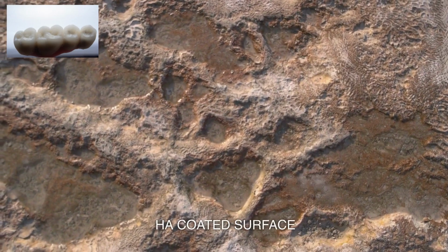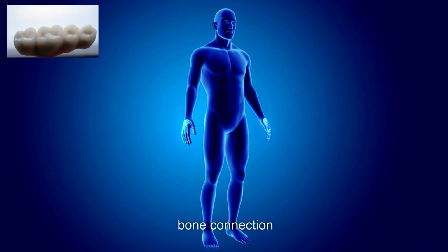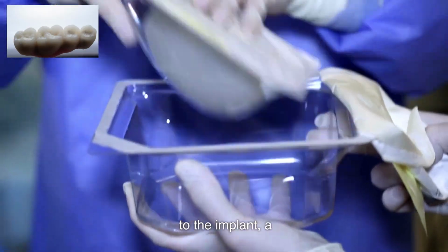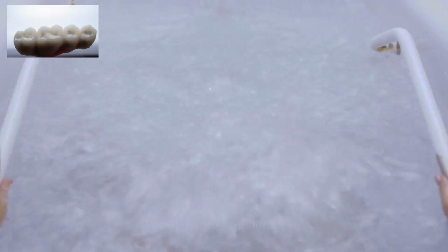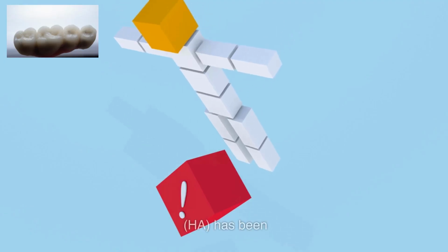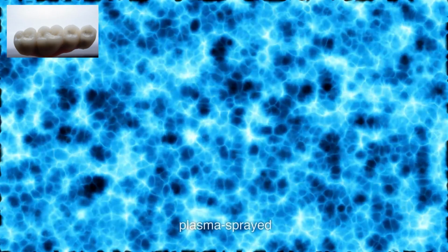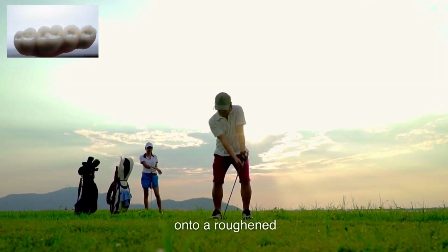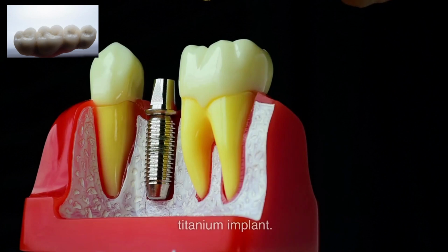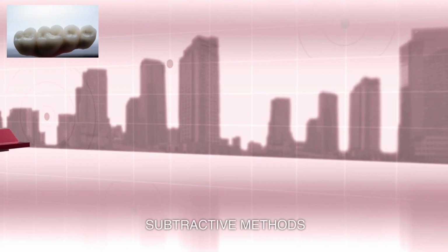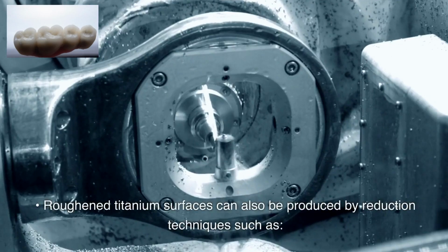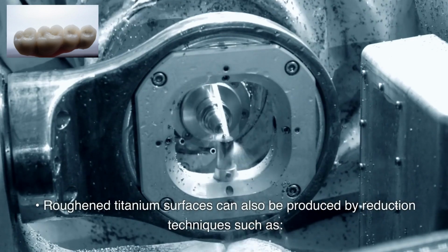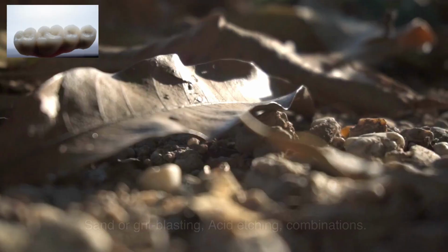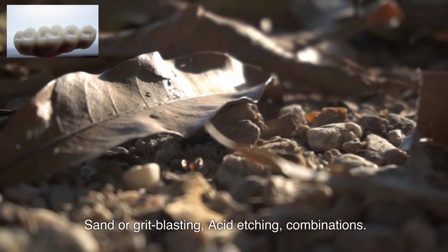HA-coated surface. In order to enhance the bone connection to the implant, a thin coating of hydroxyapatite, HA, has been plasma sprayed onto a roughened and prepared titanium implant. Subtractive methods. Roughened titanium surfaces can also be produced by reduction techniques such as sand or grit blasting, acid etching, or combinations.